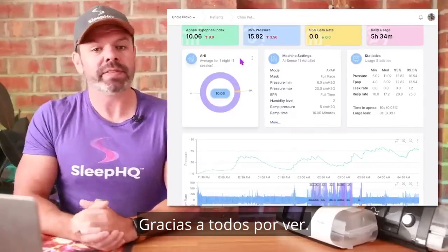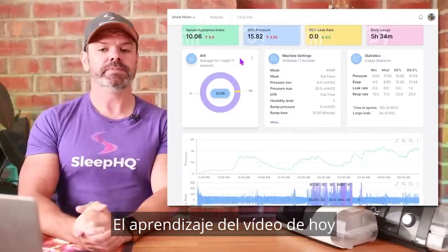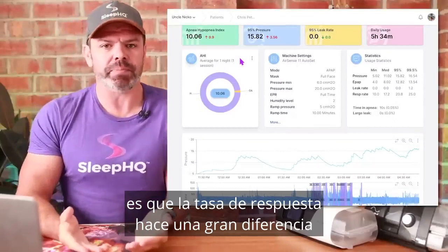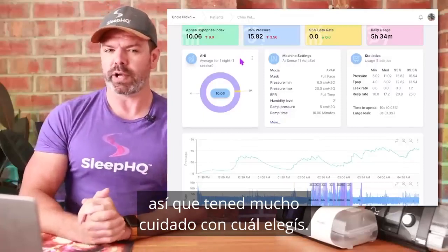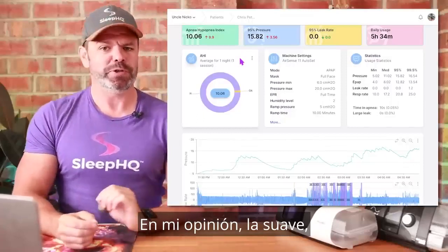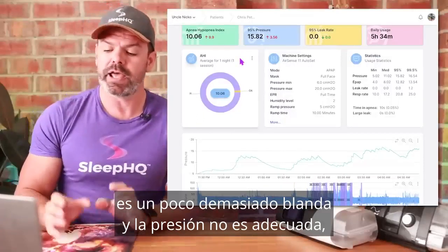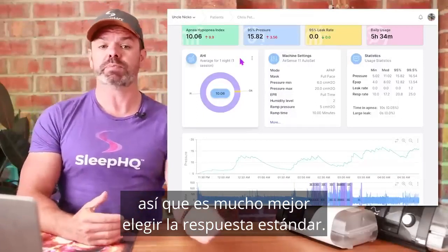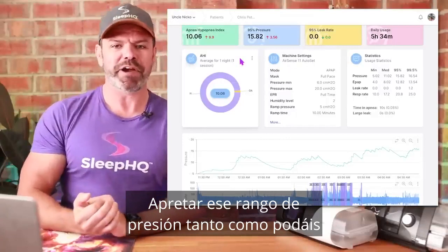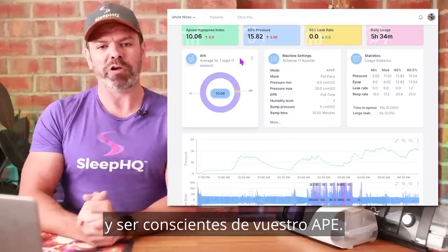Thanks for watching, everyone. The take-home message from today's video is the response rate does make a big difference to your results. So be very careful which one you choose. In my opinion, the soft, she's a little too soft, and the pressure is not adequate. So you're much better off choosing the standard response. Tighten up that pressure range as much as you can, and be mindful of your EPR.